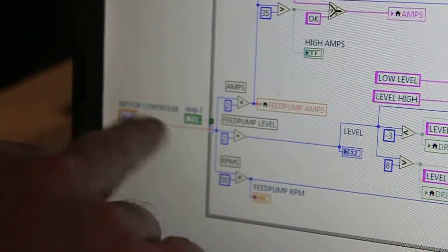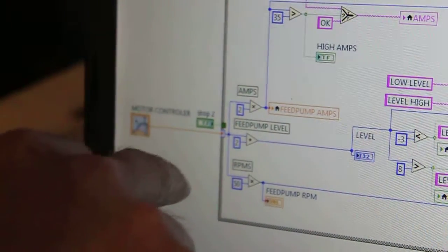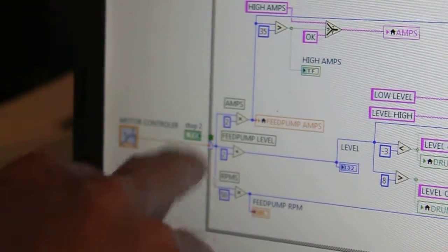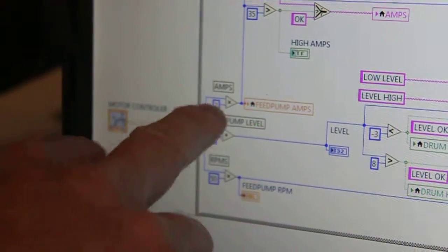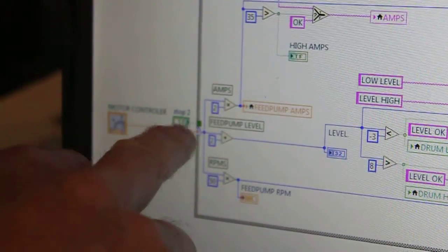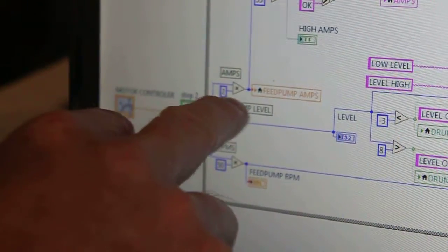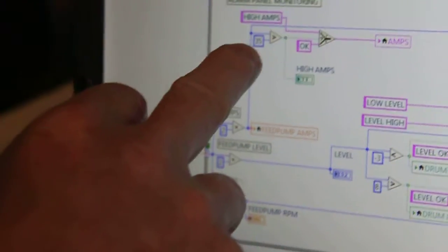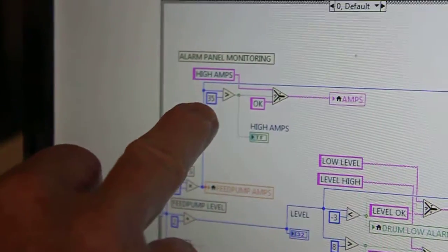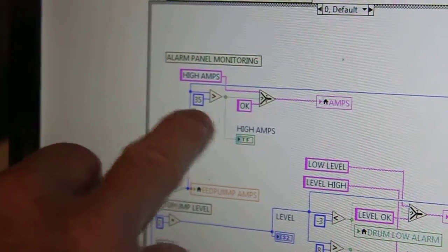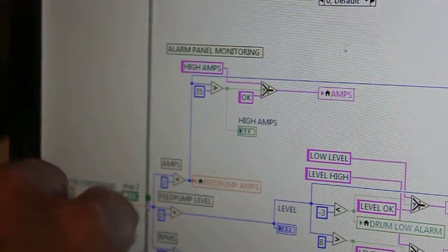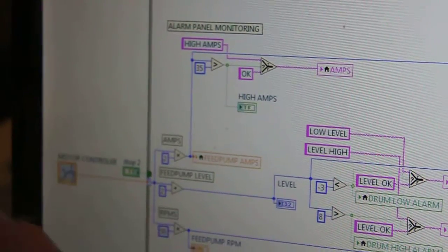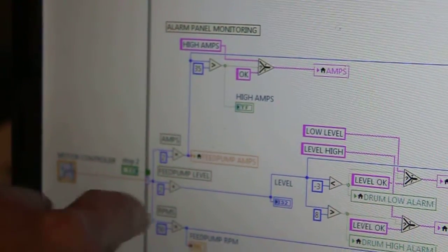So we've got the feed pump that feeds in. We've got a case structure here on the default case. What we've got is a multiplier that takes this value here, a predetermined multiplier that gives an amperage value, which is being monitored, and if that gets out of range, I've got a set point of 35 amps, then you'll get an alarm on the front panel.